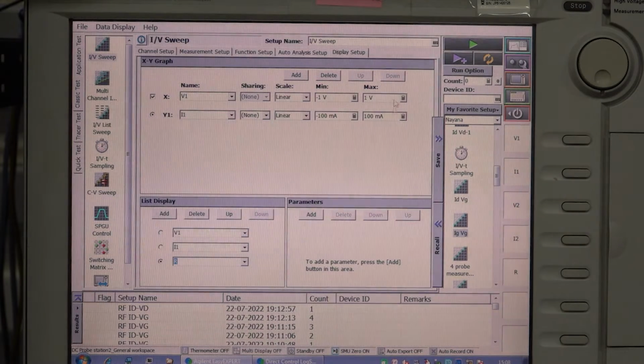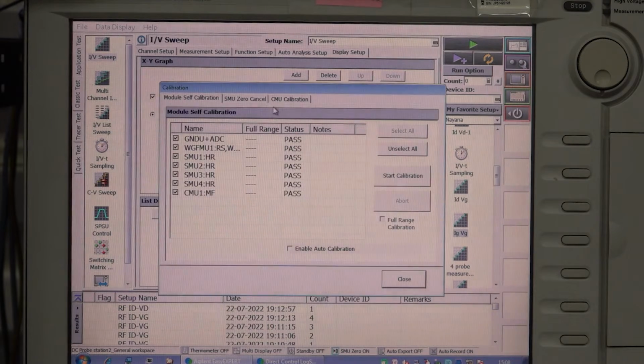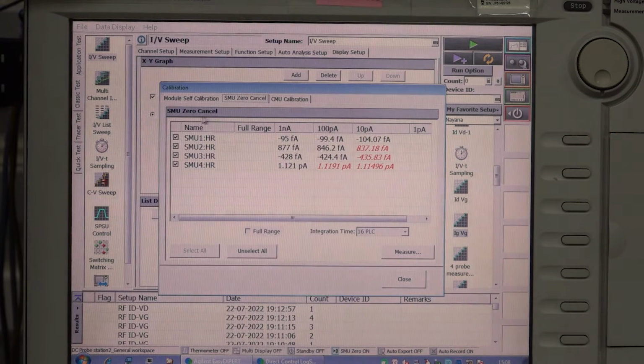So now I have set up the measurement setup, but before this I need to calibrate the instrument. In the calibration part I have SMU source, SMU zero cancel. Basically we have 4 source measuring units, and I will be measuring my devices in any one of these ranges, so I have to calibrate this particular range. Say from 1 nano to 10 pico, because these are very important low current measurements. If low current measurements are not calibrated, it will add to the measurement, which will be erroneous measurements. So I will measure this so that the instrument will subtract these values from the SMUs after measurements. This is called SMU zero cancel.